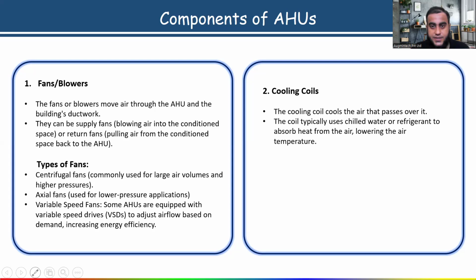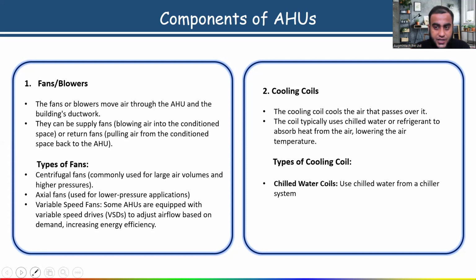And the second one is the chilled water system. In a chilled water system, the supply air is cooled by a secondary refrigerant. Secondary refrigerant means the refrigerant which changes temperature during the cycle, for example water, brine, glycol. So if water is running inside the coil, that is your secondary refrigerant. If you cool the supply air with the help of that water, that is called a chilled water system. Is it clear? So we have different types of cooling coil, like the chilled water coil, which uses chilled water from a chiller system. The direct expansion coil uses refrigerant directly for cooling. Is it clear, all of you? Understood? Tell me, please, so we can go further.